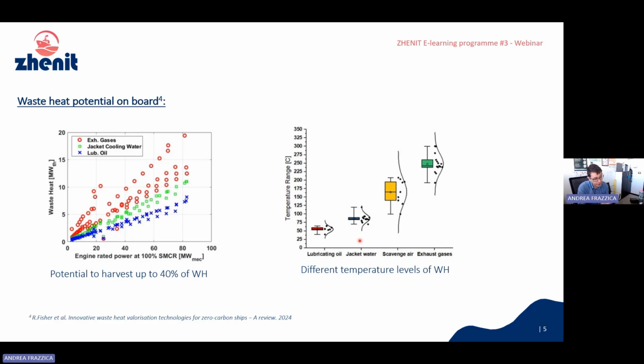We identified three main sources of waste heat: lubricating oil, jacket water (the cooling water of the engine), and all the energy contained inside the exhausted gases, either from the scavenged air or the exhausted gas directly. Of course, if we increase the temperature in general, we also have more energy to recover.